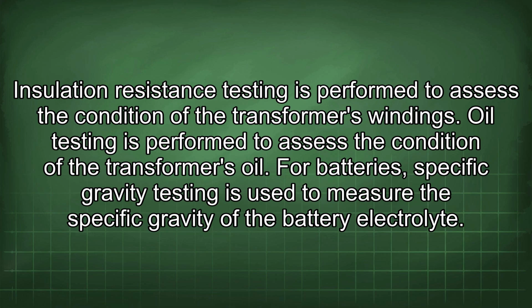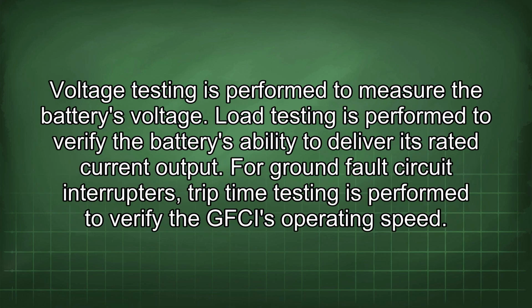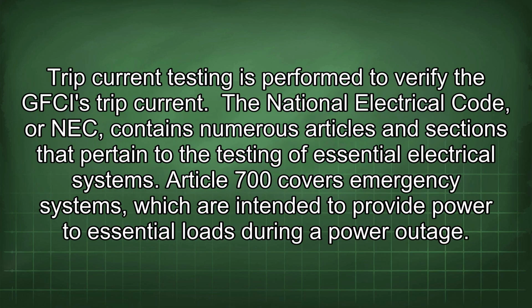For batteries, specific gravity testing is used to measure the specific gravity of the battery electrolyte. Voltage testing is performed to measure the battery's voltage. Load testing is performed to verify the battery's ability to deliver its rated current output. For ground fault circuit interrupters, trip time testing is performed to verify the GFCI's operating speed. Trip current testing is performed to verify the GFCI's trip current.